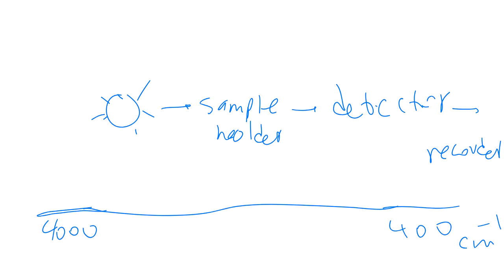The sample holder for IR takes a very small sample. Traditionally, samples were mixed with KBr or NaCl pellets and pressed into thin layers under high pressure. Newer sample holders have two pieces of diamond — you place a small sample and screw the top, compressing it into a very thin layer through which the light shines.